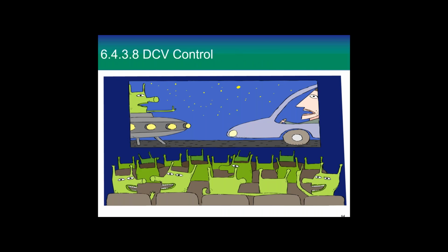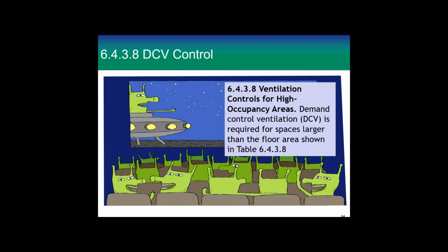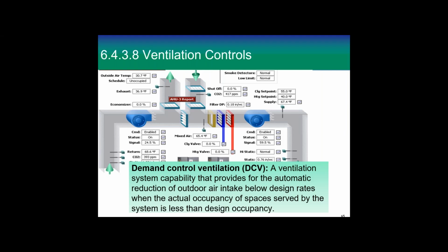Now, we require demand control ventilation in certain circumstances. So ventilation controls for high occupancy areas. Demand control ventilation is required for spaces larger than the floor area shown in table 6438. And here, this table is a new thing for 2022. So we'll explain the ventilation control a little bit. Demand control ventilation is a ventilation system capability that provides for the automatic reduction of outdoor air below design rates when actual occupancy of spaces served by the system is less than design occupancy.